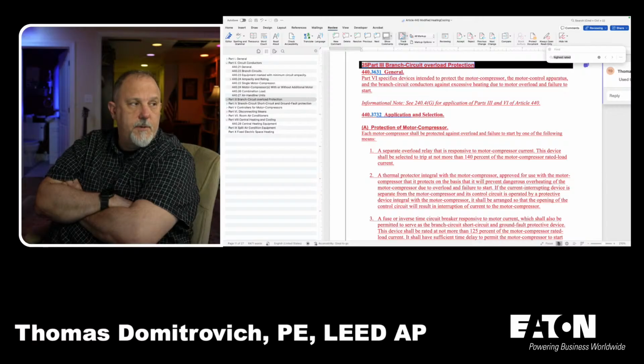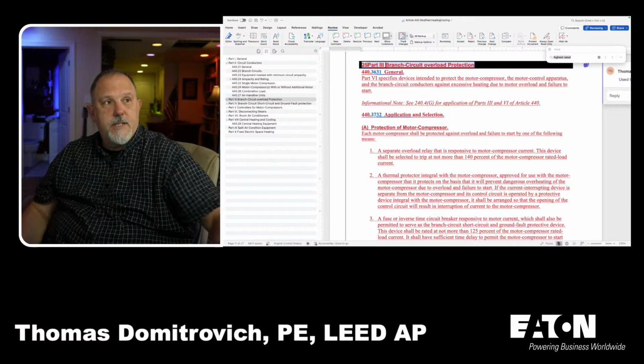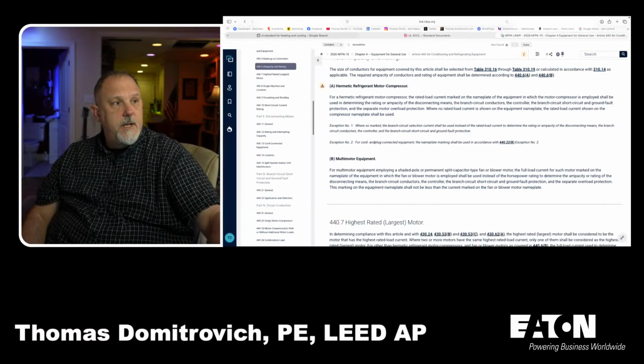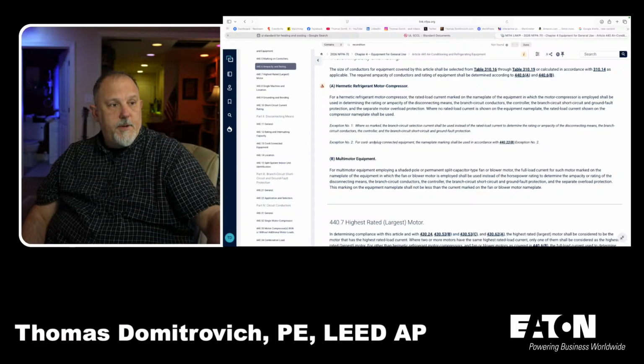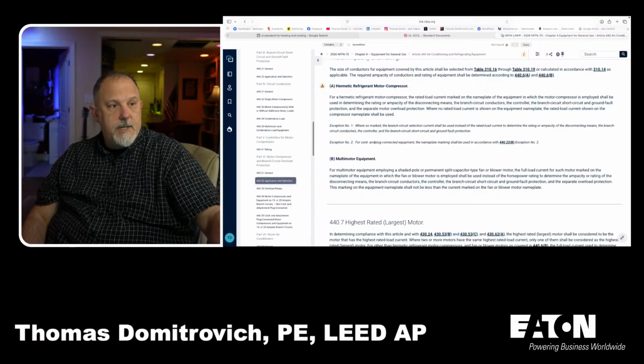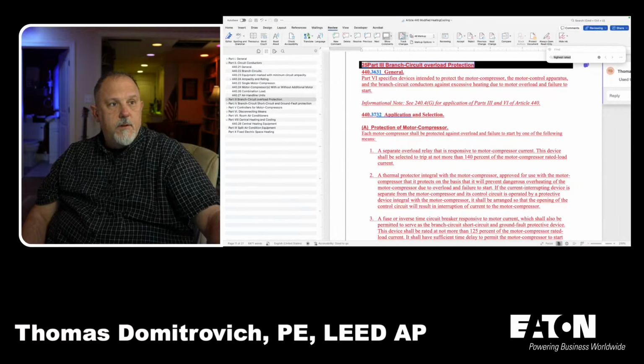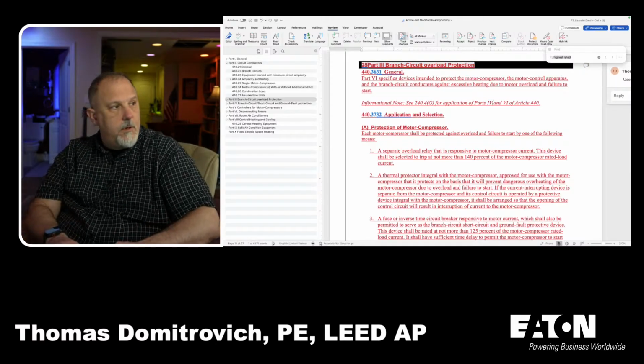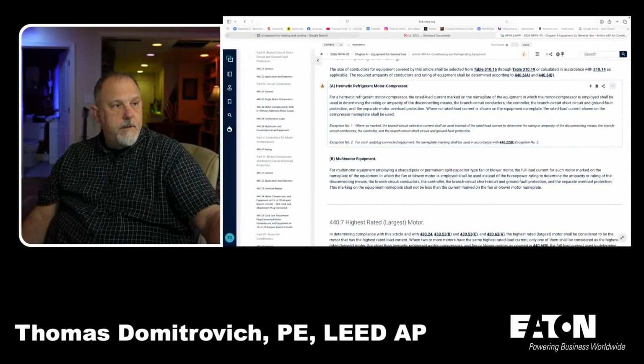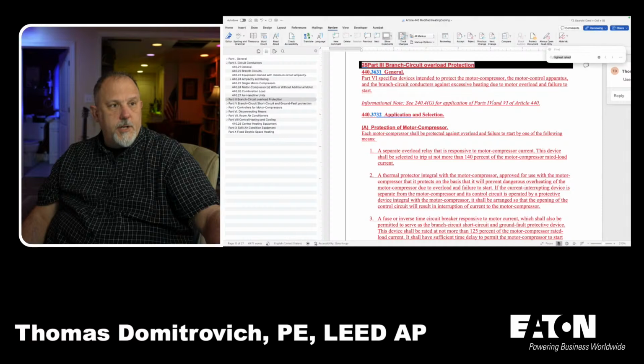See 240.4(G) for application of parts 3 and 6 of Article 440. I hope those are right. Parts 3 and 6 of 440. What were parts 3 and 6 of 440? Part 3 is branch circuit, short circuit, and ground fault, and 6 is motor compressor. Branch circuit, short circuits, part 4. Part 4, and motor compressor and branch circuit overload protection, part 3.